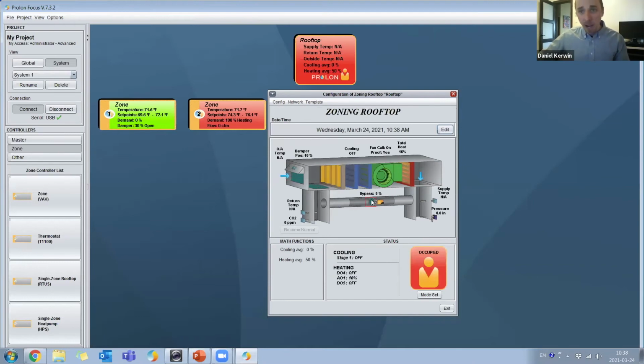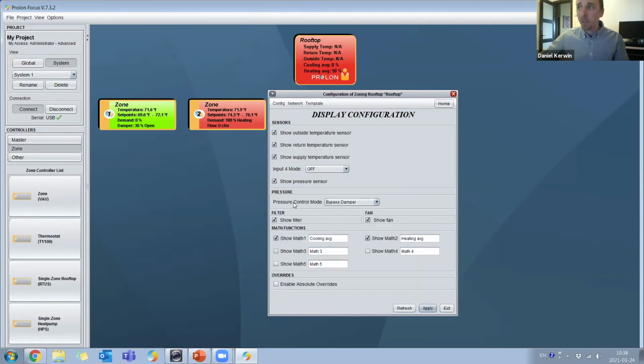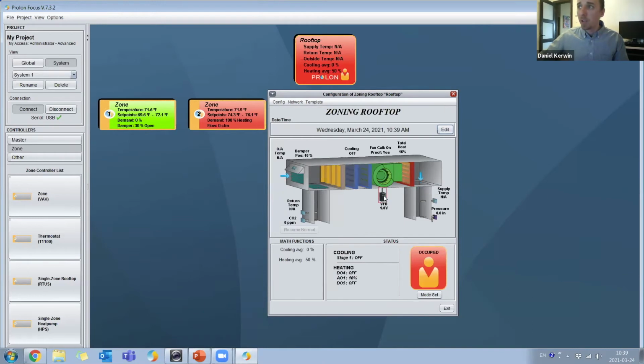So in this case, we have a bypass damper, which would traditionally be seen in a zoning system, and more specifically a VVT zoning system. But nowadays, it is becoming much less prevalent, and so what we're seeing a lot more is variable frequency drives instead. So we are able to change that very quickly on our software just by doing config, edit display, pressure control mode. I won't choose bypass. I'll just choose a variable frequency drive right here. I will press on apply, go home, and then here's the VFD, which pops up automatically right there.